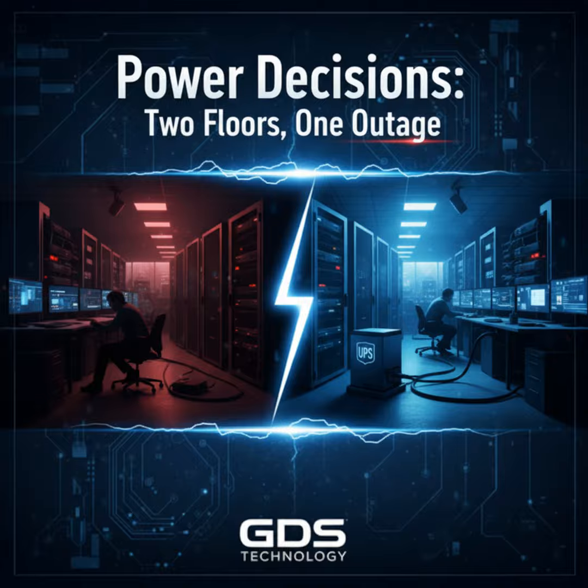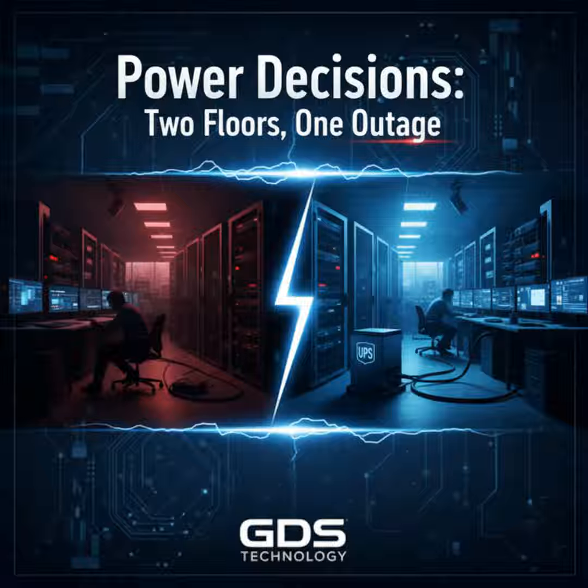A few realistic trade-off examples. Sometimes adding a modest UPS that covers only comms closets and access control is far cheaper and operationally simpler than upsizing the generator to supply whole-floor HVAC. Other times, a tenant with a small lab or compute cluster will need tenant-funded redundancy that they manage themselves. There's no one-size-fits-all answer. There's only the right answer for your risk tolerance, budget, and staffing model.